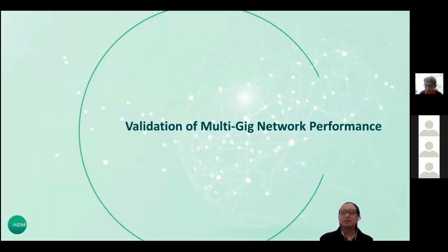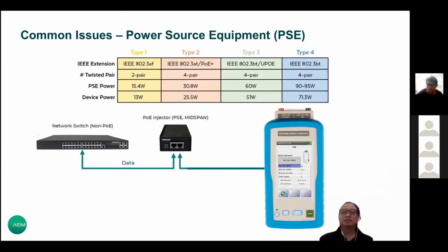So we come to the second question. What is the accuracy of the PoE watt measurement? The accuracy of the PoE comes from the power supply. That is usually the spec of the PoE power source equipment that you buy. For example, if you buy an injector, it comes with either 30 watt, 60 watt, 90 watt, or even a 51 spec. The accuracy comes from the standard itself, the PoE IEEE standard. The IEEE standard says your output power should have a minimum. For 15 watt it is 13 watt. For 90 watt it is 71 watt. So this, I would say, is more or less the accuracy of the wattage.